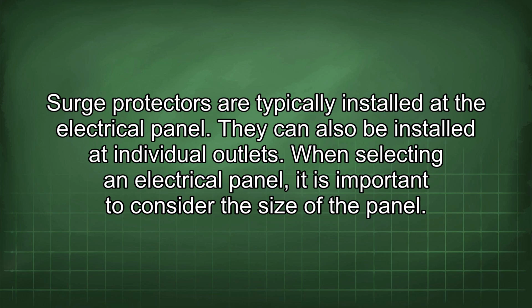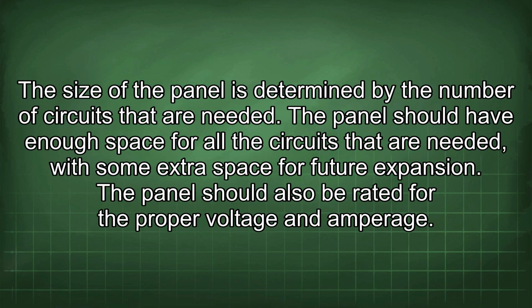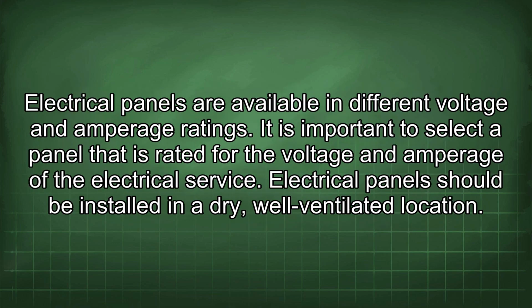When selecting an electrical panel, it is important to consider the size of the panel. The size of the panel is determined by the number of circuits that are needed. The panel should have enough space for all the circuits that are needed, with some extra space for future expansion. The panel should also be rated for the proper voltage and amperage. Electrical panels are available in different voltage and amperage ratings. It is important to select a panel that is rated for the voltage and amperage of the electrical service.